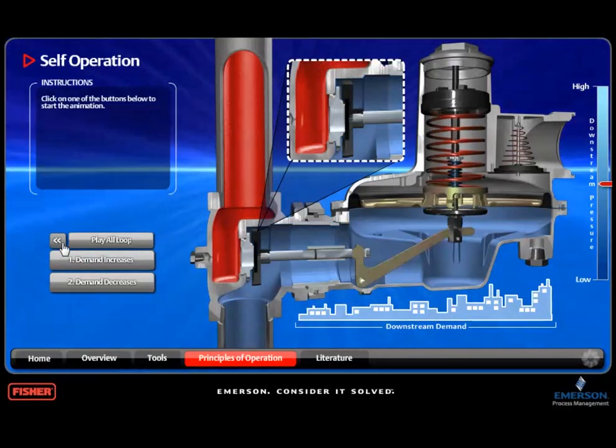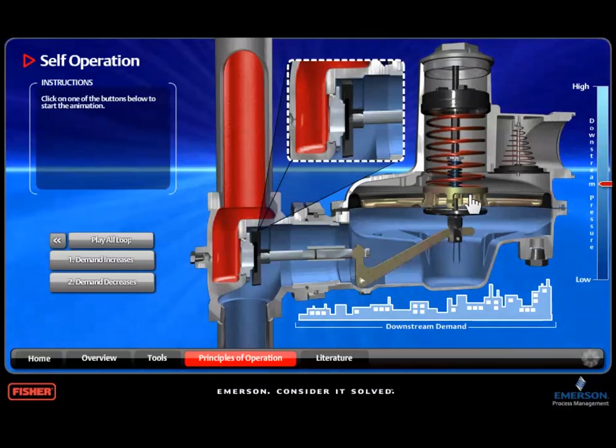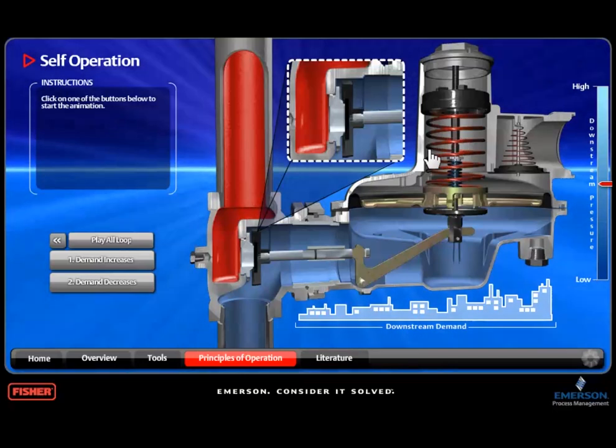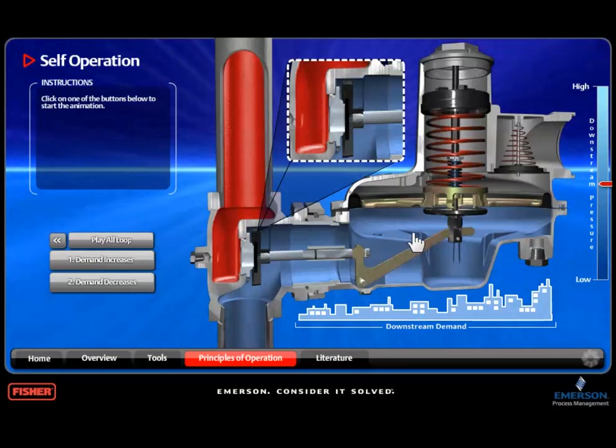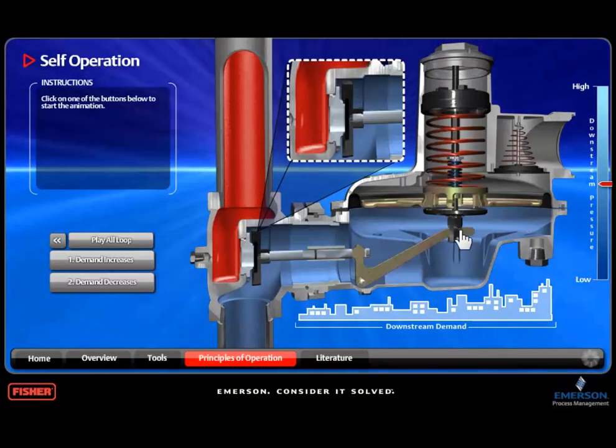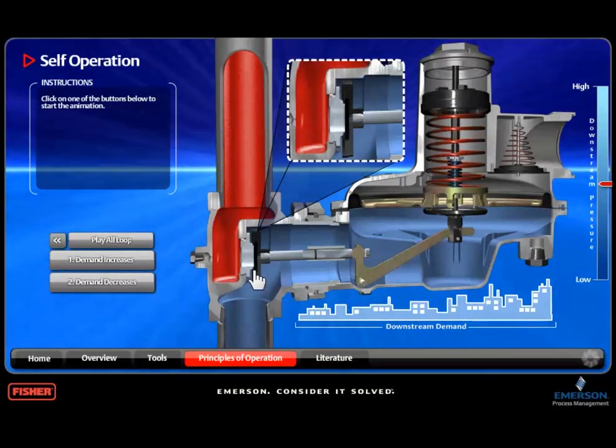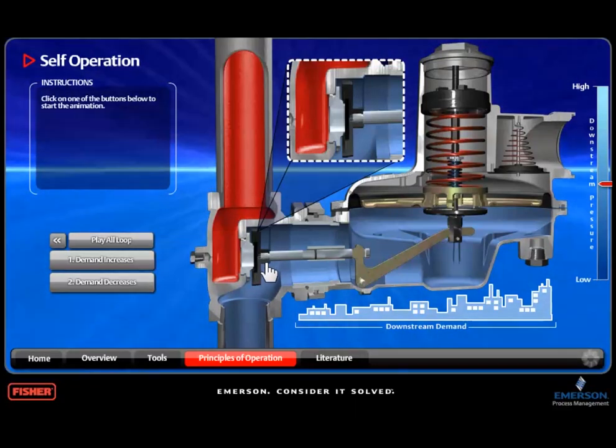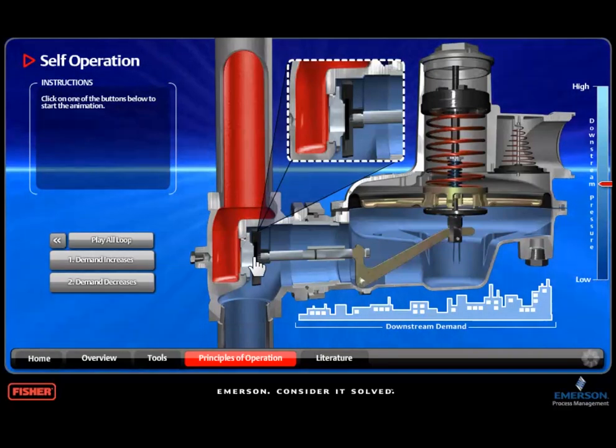This regulator is composed of a diaphragm, which is an elastomer material with a spring on the upper side and outlet pressure shown in blue on the bottom side. The diaphragm is connected by a lever to the valve disc or seat, which can restrict flow by moving towards the orifice or away from the orifice to allow gas flow from the inlet side shown in red.